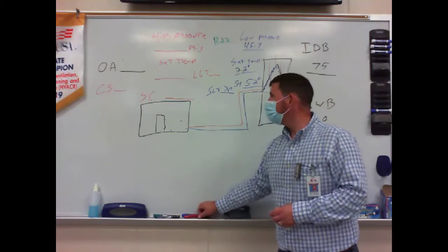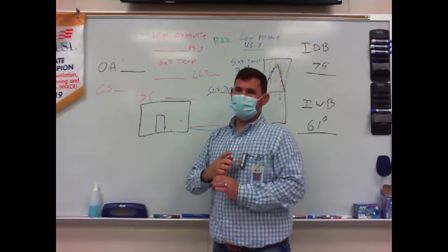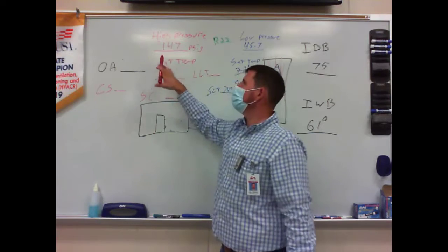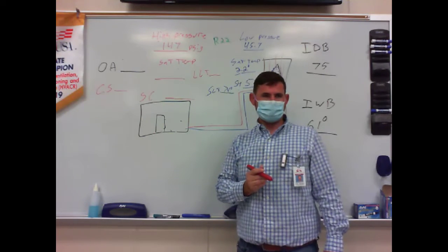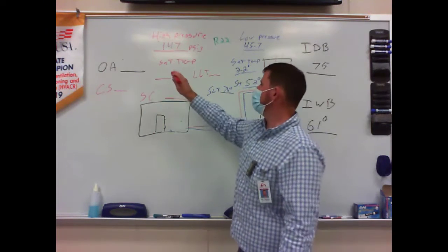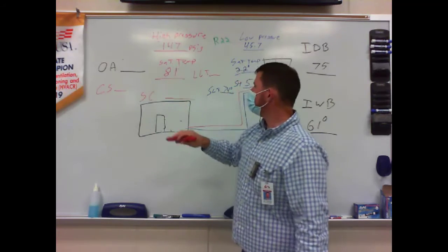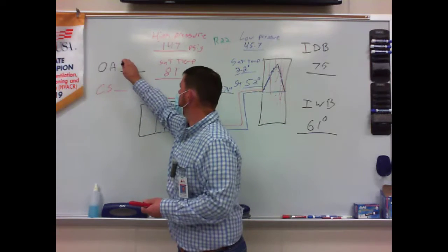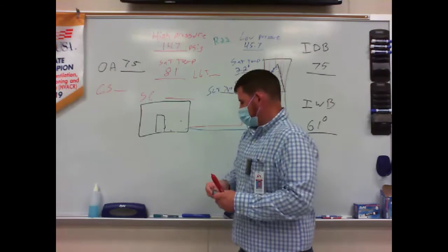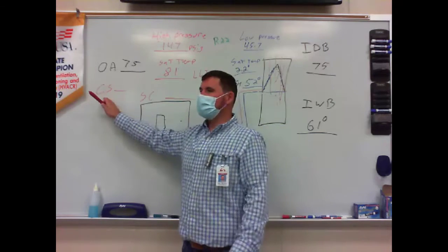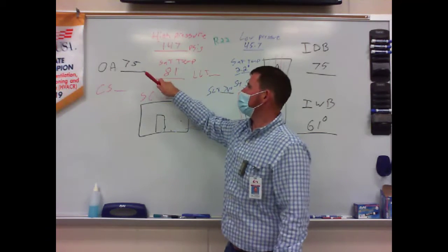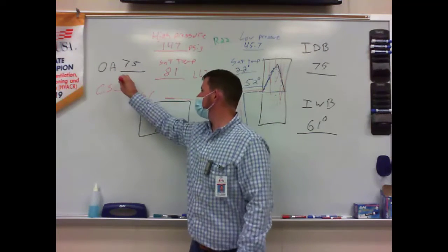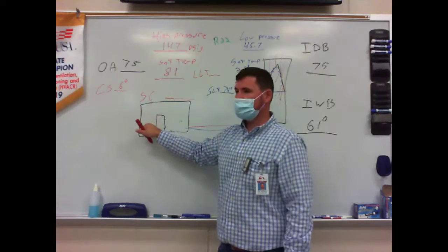Let's get our numbers. High side pressure was 147 psi. So in R22, what am I saturating at? 81. What was my outdoor ambient temperature? So my condenser split, or how much warmer am I saturating above the outside air? 6 degrees. Is my condenser very warm?